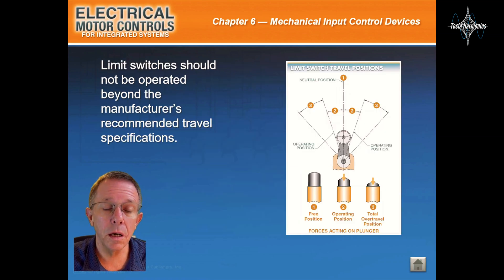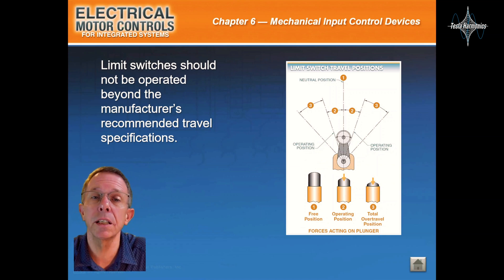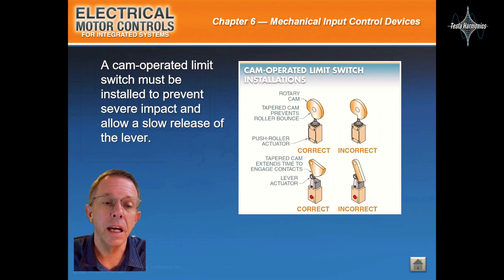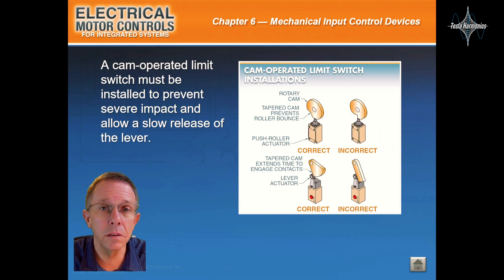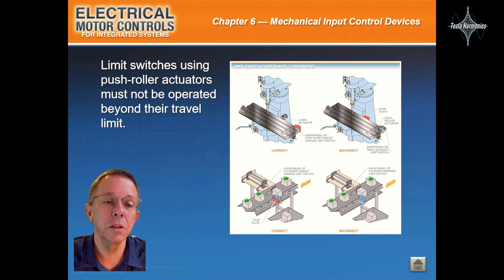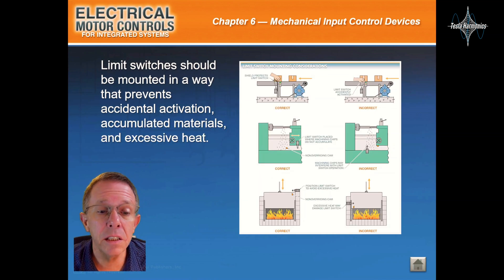Limit switches should not be operated beyond the manufacturer's recommended travel specifications. A cam-operated limit switch must be installed to prevent severe impact and allow a slow release of the lever. Limit switches using push roller actuators must not be operated beyond their travel limit. Limit switches should be mounted in a way that prevents accidental activation, accumulating materials, and excessive heat.